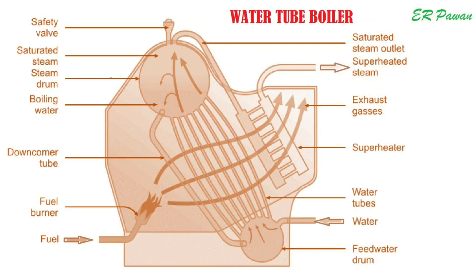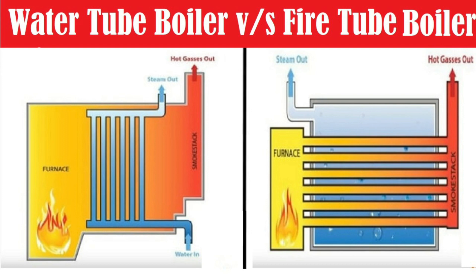In this slide you can see the water tube boiler. Water flows through tubes that are surrounded by hot combustion gases in a shell, usually rated in tons of steam per hour, and used for high-pressure steam and high capacity. In recent years, interest has been revived in high-temperature hot water heating systems for institutions and industrial and commercial plants, by increasing the temperature and pressure of the hot water and increasing the size of generators, gaining some advantages over the low-pressure steam heating system previously used.